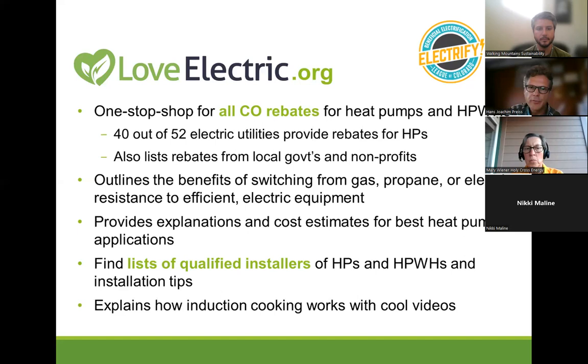So if you have an older gas tank type, 80% efficient, that is atmospheric combustion, so you have a hole in your wall, it can backdraft when you run your bathroom fan, so you want to get rid of this dinosaur. Those are not only inefficient, they are dangerous as homes become more airtight. If you have a combi boiler or a tankless gas water heater, those are typically sealed combustion. Those are safe. I'm not saying that the other ones are unsafe, but they can lead to unsafe conditions.